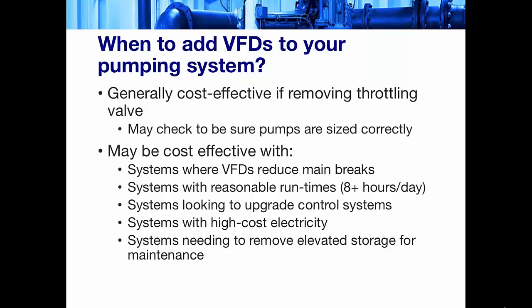themselves aren't too big. And then it may also be cost effective in various high main break situations, if you have pumps that run quite a few hours a day, if you're otherwise looking to automate or upgrade your control systems, if you have very high cost electricity, the savings can come pretty fast. And then also variable frequency drives are very useful if you have to remove your elevated storage for maintenance. Your variable frequency drive and the control system can basically keep a consistent operating pressure in most distribution systems without the need for an elevated tower. So you can run for a couple weeks while the tower undergoes maintenance and repairs.